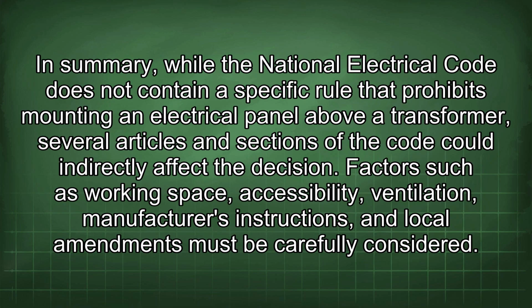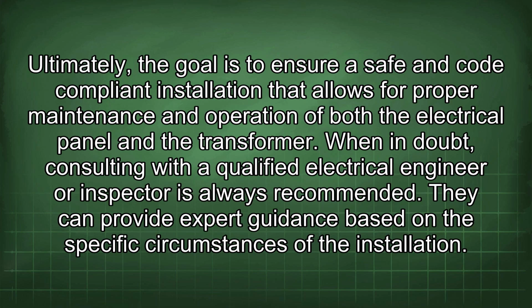In summary, while the National Electrical Code does not contain a specific rule that prohibits mounting an electrical panel above a transformer, several articles and sections of the code could indirectly affect the decision. Factors such as working space, accessibility, ventilation, manufacturer's instructions, and local amendments must be carefully considered. Ultimately, the goal is to ensure a safe and code-compliant installation that allows for proper maintenance and operation of both the electrical panel and the transformer. When in doubt, consulting with a qualified electrical engineer or inspector is always recommended. They can provide expert guidance based on the specific circumstances of the installation.